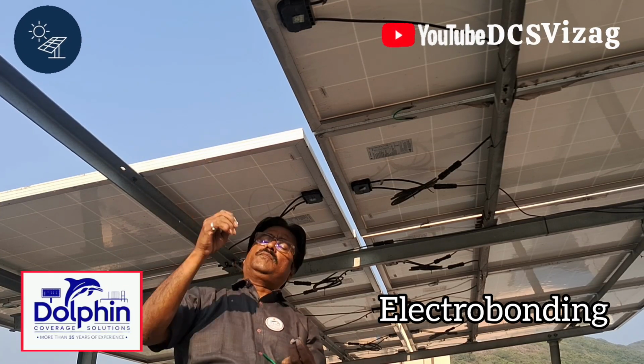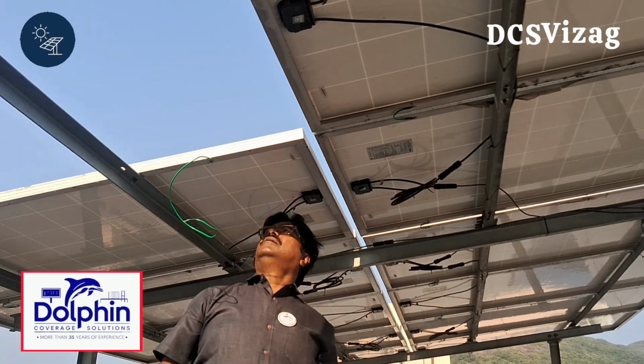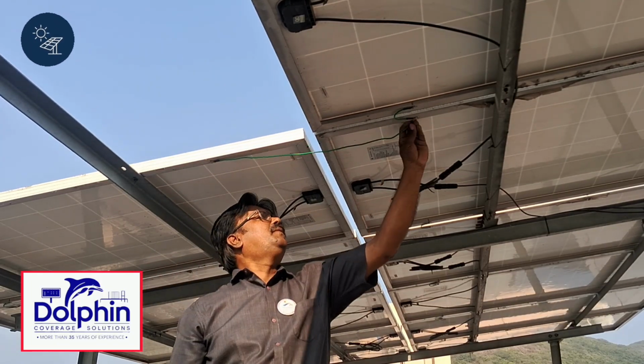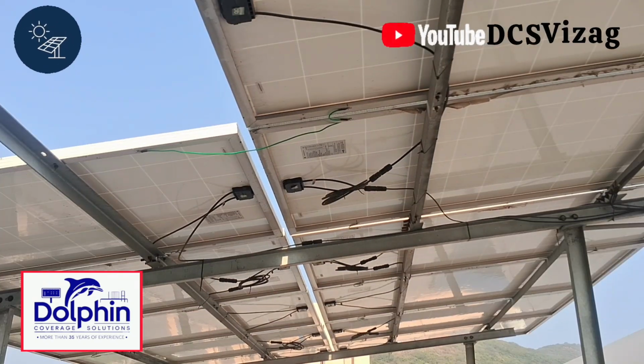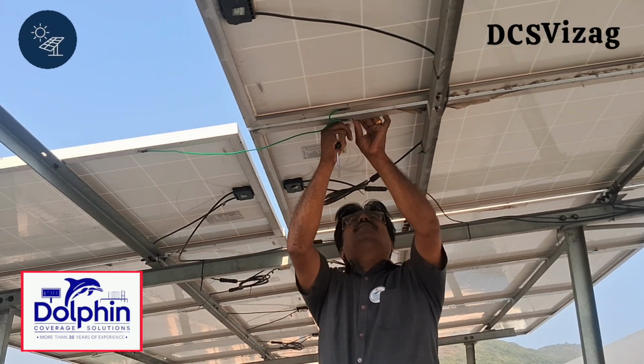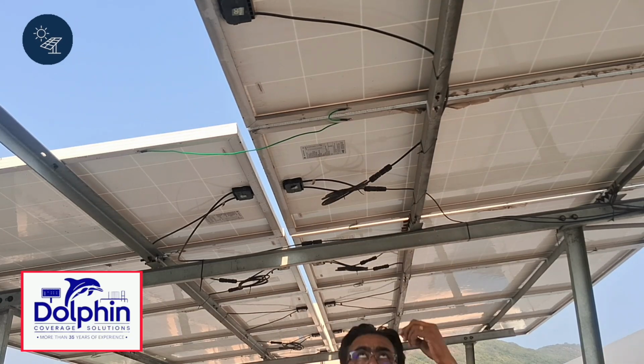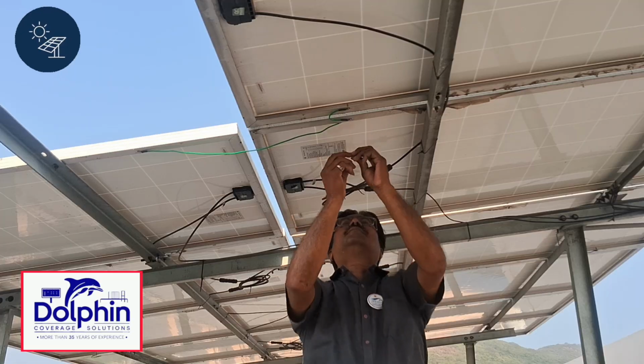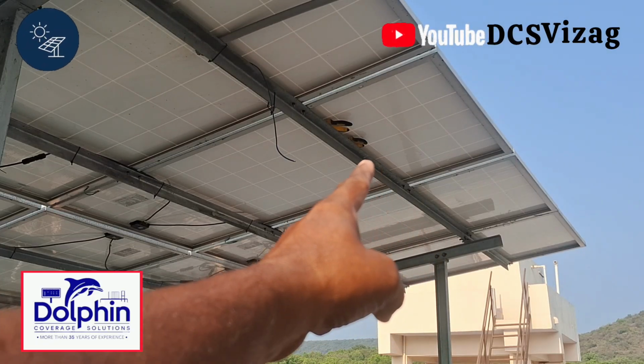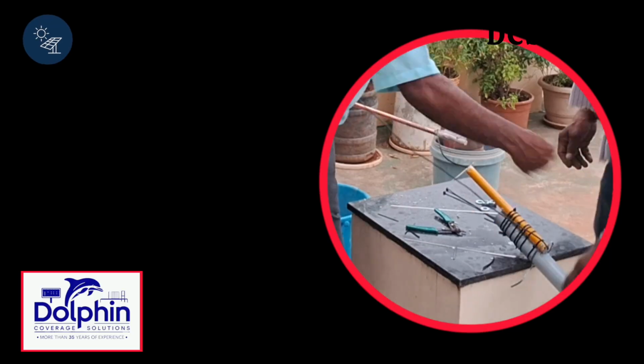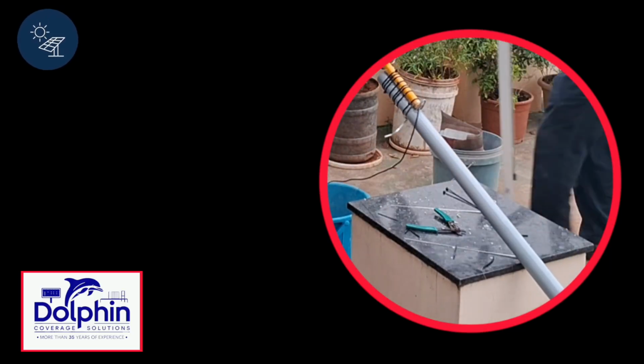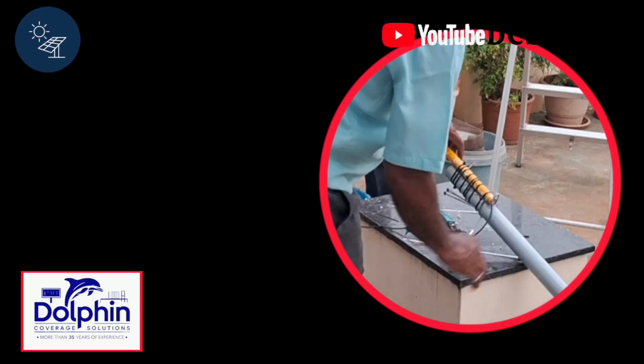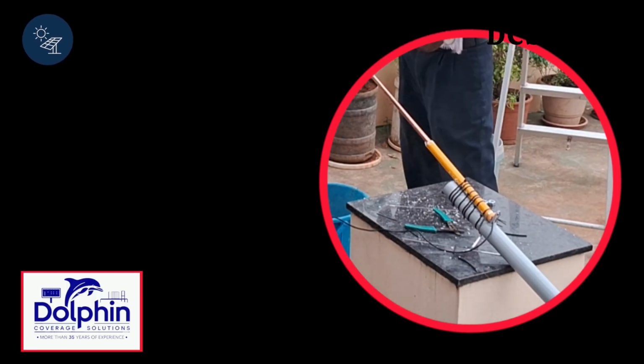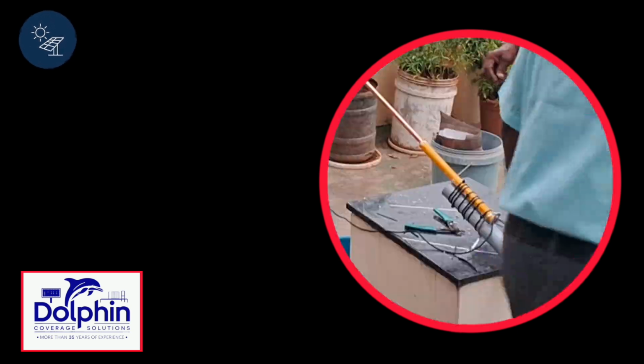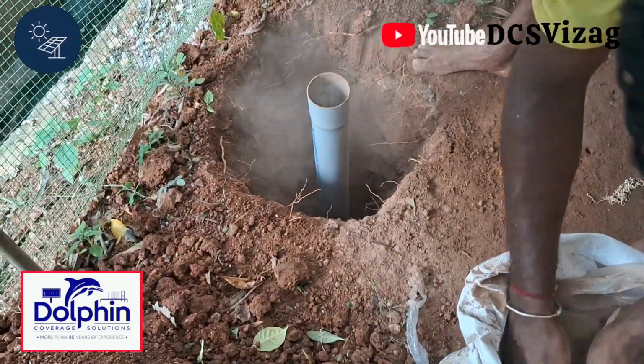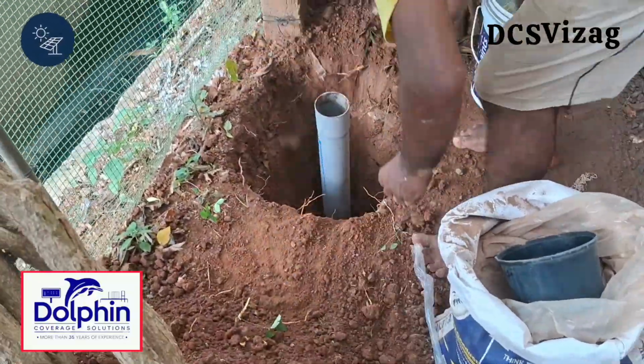Connections. Panel frame bonding. All metallic frames of the solar panels in an array should be interconnected and bonded to the DC earthing system. This can be done via the mounting structure if it is designed for electrical continuity, or with dedicated grounding clips, plugs, and a continuous copper earthing cable running along the panel rows. Inverter and electrical equipment bonding. Connect the chassis of the inverter, ACDB, DCDB, and other metallic enclosures to their respective earthing points using appropriate copper wires or strips. Lightning arrestor connection. The lightning arrestor, if used, should have a direct, low resistance path to its dedicated earth pit.